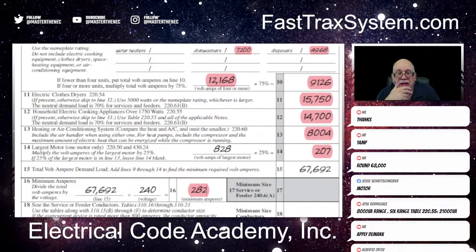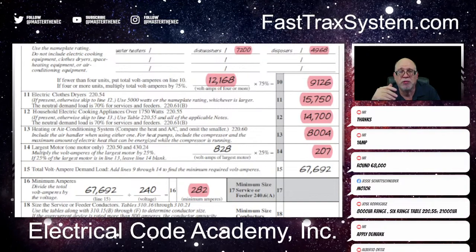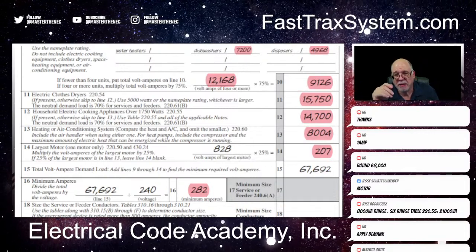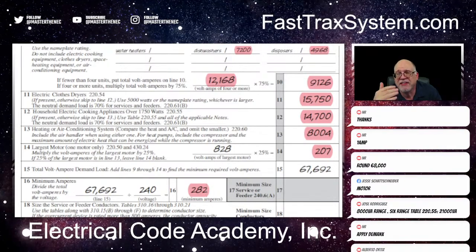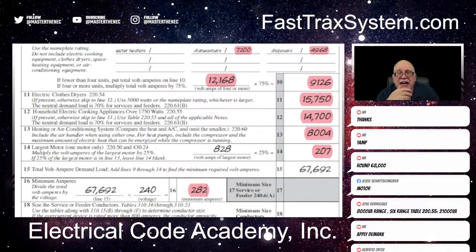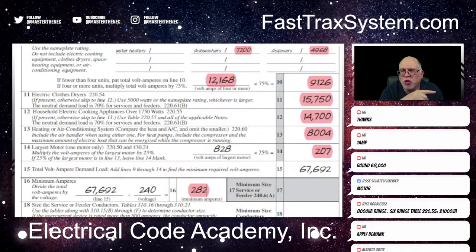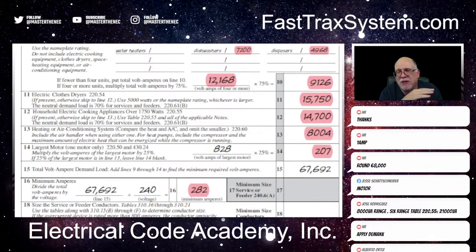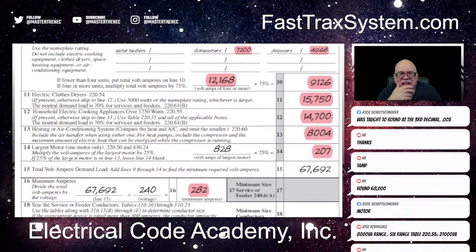Now, when it comes to the end amp value, I typically wouldn't round up. I drop off. So in this case, I'm dropping off. It shouldn't make any big difference how you want to do it. To be perfectly clear, 220.5 tells you that you can only round amps. So I tell most people, don't round. I won't mark it wrong most of the time, except for neutral. For a branch circuit neutral contribution, if it says I want the pure contribution, then I don't like you to round. But any other time, I don't really care if you round. It shouldn't change anything, okay?